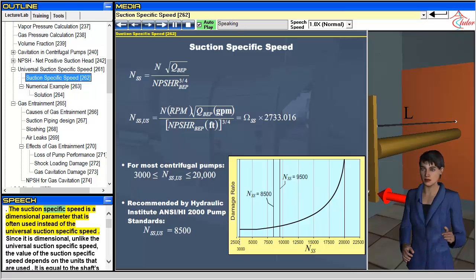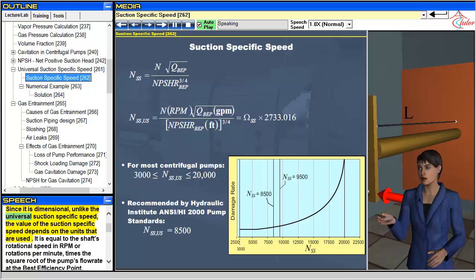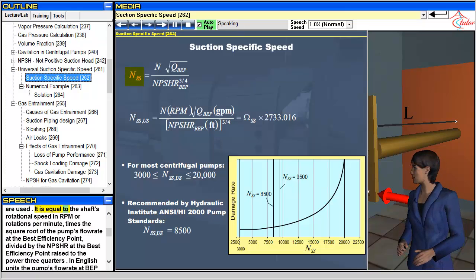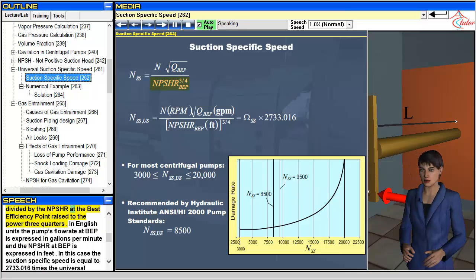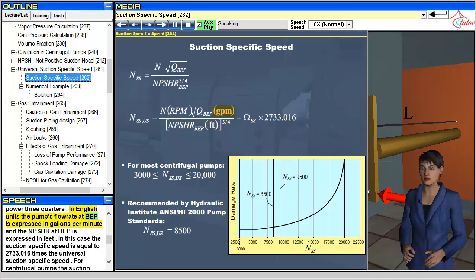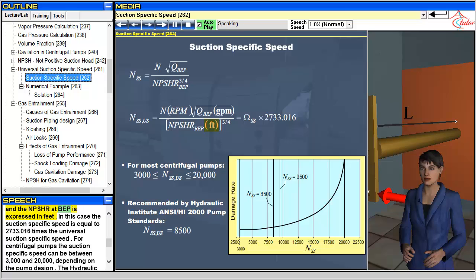The suction-specific speed is a dimensional parameter that is often used instead of the universal suction-specific speed. Since it is dimensional, unlike the universal suction-specific speed, the value of the suction-specific speed depends on the units that are used. It is equal to the shaft's rotational speed in rpm times the square root of the pump's flow rate at the best efficiency point, divided by the NPSHR at the best efficiency point raised to the power three quarters. In English units, the pump's flow rate at BEP is expressed in gallons per minute, and the NPSHR at BEP is expressed in feet.